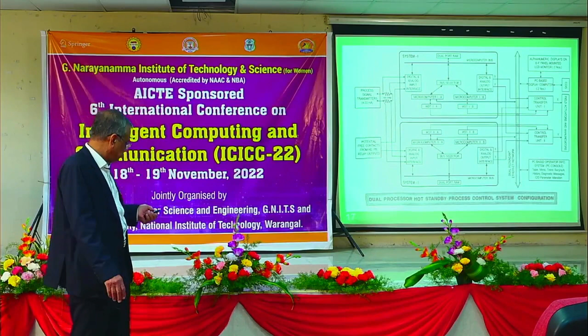This is the actual system, which was manufactured at Electronics Corporation of India Limited, Hyderabad. This is a photograph taken from ECIL only, not at the plant where it is being tested. Performance, reliability, safety and availability requirements are met by employing a fault tolerant computer architecture like DPHS, using in-house developed microcomputer hardware with facility of online diagnostics, and redundancy in DC power supply and AC power connections, as I have explained. Input and output isolation for both analog and digital: analog input transformer isolation, similarly output also transformer isolation. Fail safe outputs I explained, and a dual redundant network, independent network with the plant computer.